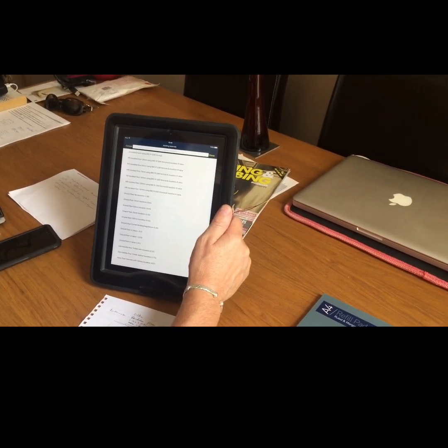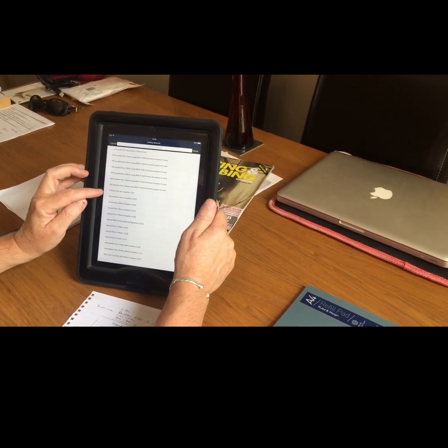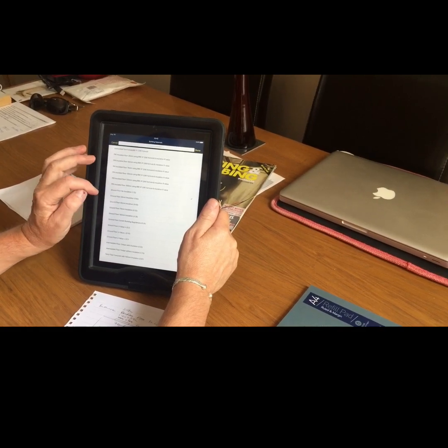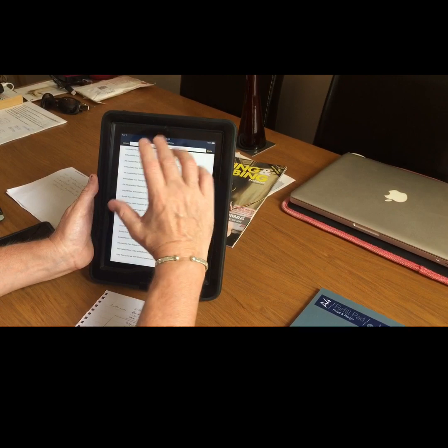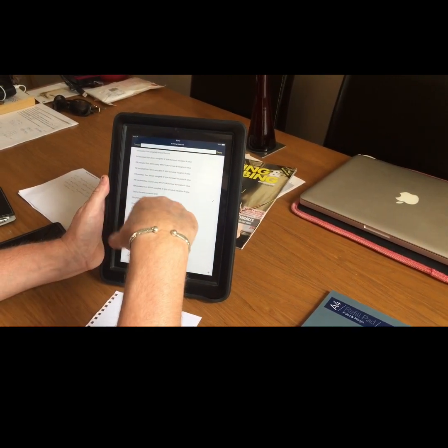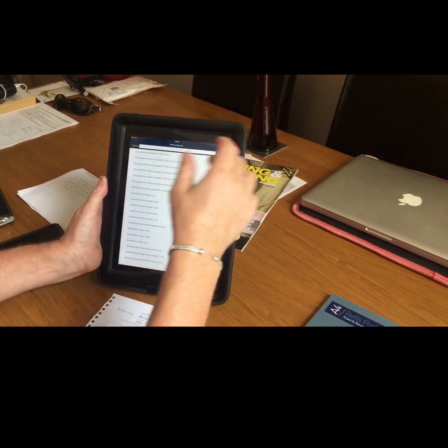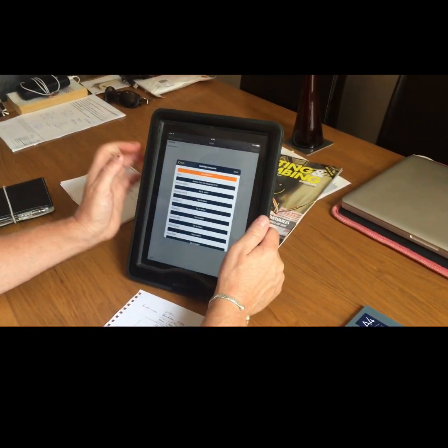Do we know? No insulation. So we're looking at a ground floor, no insulation. The U value of that is calculated at 1.15. For this purpose, that's how we're going to do it. You can get much deeper into this, and you can also customise the U value and the floor construction should you require. But most surveyors would know what that structure is.